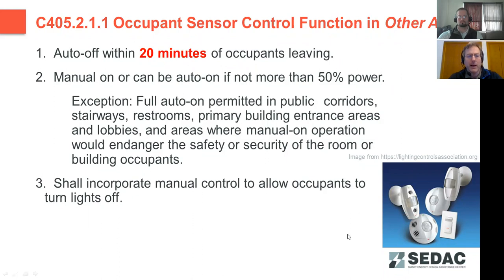So that allows occupants, as they enter the room, to either determine, do I need lights at all, or if they walk into a space and the lights come on to 50% power, the occupant can choose if they want to go ahead and bring it all the way up to 100%, or maybe they prefer it at 50% is fine. The code does provide some exceptions for the auto on to allow lighting to come to 100%. So here noting corridors, stairways, restrooms, and other potential safety issues here.